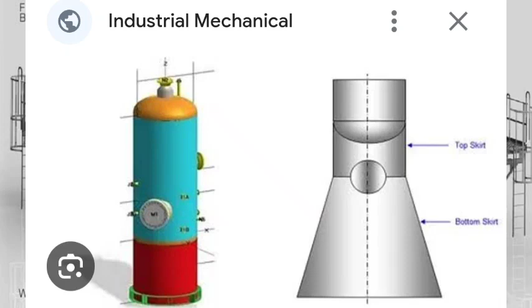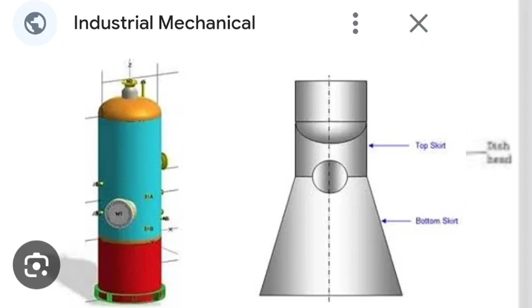So the skirt is CS, right? If the length of that skirt is 2000, 1000 is SS and 1000 is CS. The top part is connected to the vessel, which is SS, and the bottom part is connected to the bottom. In this case, what I can see is they have avoided the dissimilar metal combination with the pressure part. The pressure part to the first skirt is made of the same material and welded with SS matching filler wire. And for strength purposes, the remaining bottom non-pressure part to non-pressure part, that is SS skirt to CS skirt, they have welded with 309 LMO.